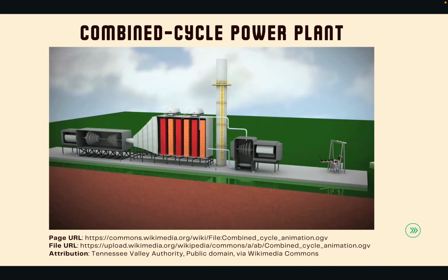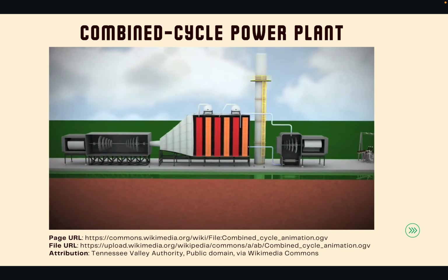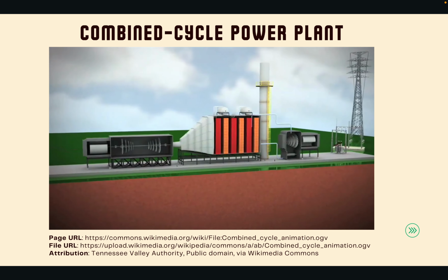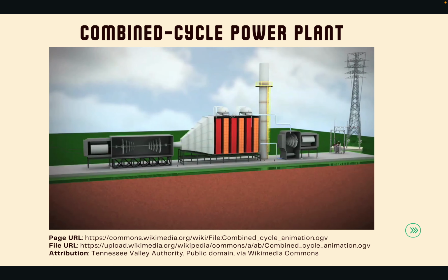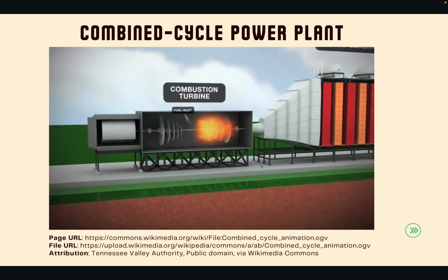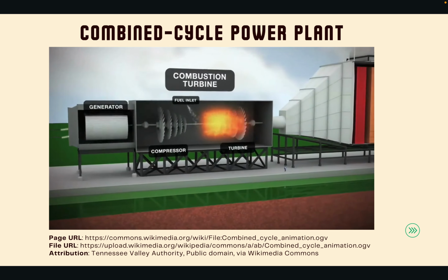Combined cycle technology enables power plants to generate 50% more electricity from its fuel than it would with a conventional single-cycle power system. Under this dual-phase system, two combustion turbine generators operate in conjunction with two heat recovery steam generators and a steam turbine generator. In the first cycle, fuel is burned and the resulting combustion gases power two turbine generators to produce electricity.